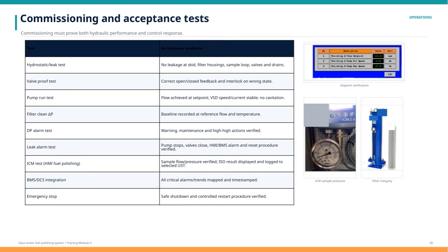The pump run test ensures that the flow meets the set point, the variable speed drive maintains stable speed and current, and there's no cavitation in the pump. Filter clean differential pressure is recorded at a reference flow and temperature to establish a baseline for monitoring filter condition over time. Alarm tests are crucial for safety and reliability. The differential pressure alarm test checks that warnings and maintenance alerts work properly, including high alarm actions. The leak alarm test confirms that if a leak is detected, pumps stop, valves close, and alarms activate on both the HMI and the building management system, with a proper reset procedure in place.